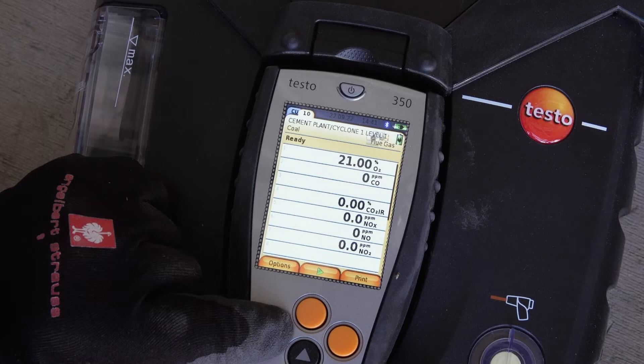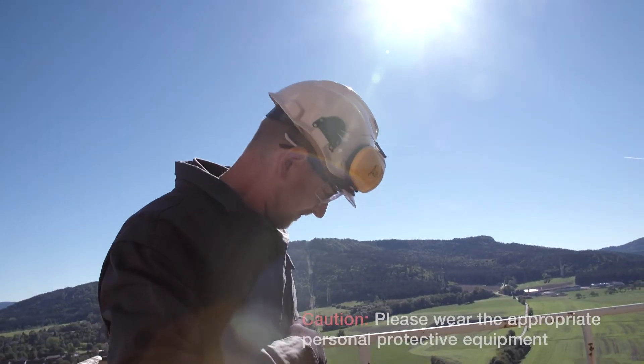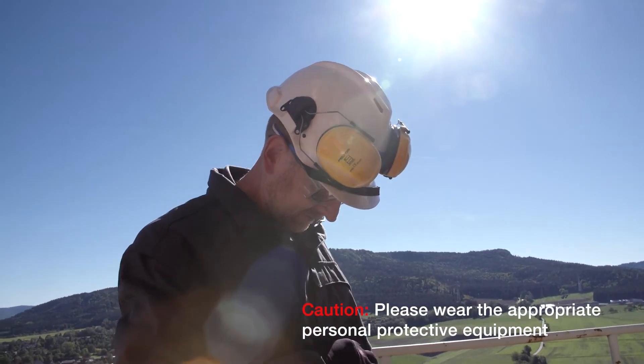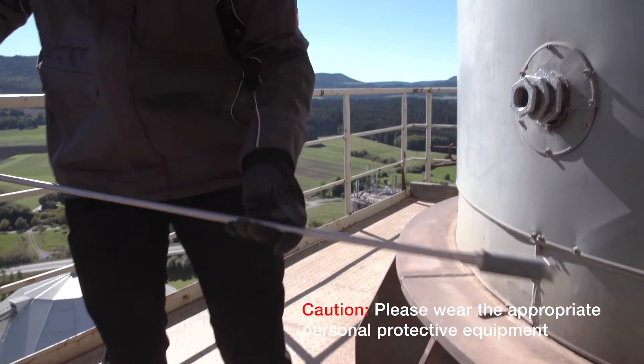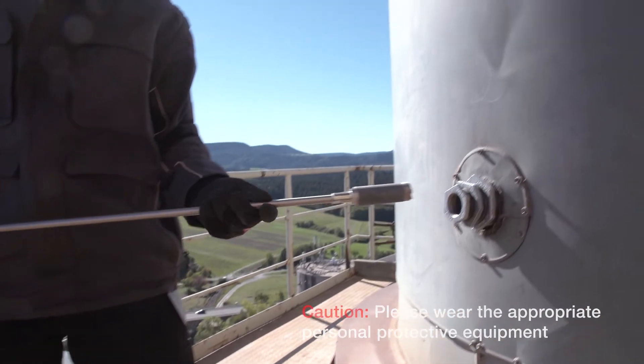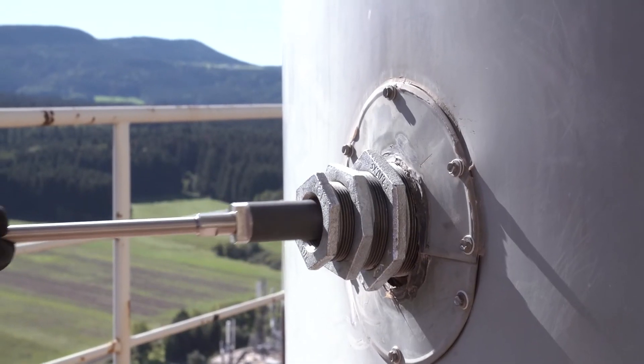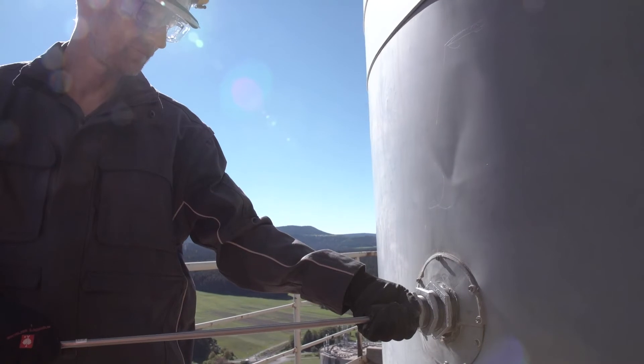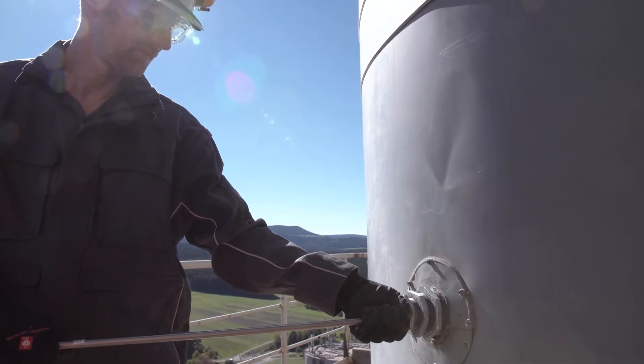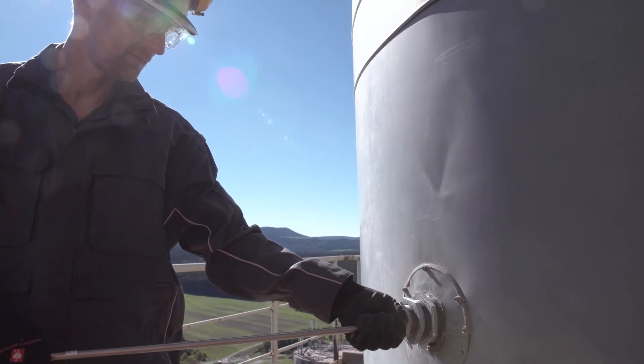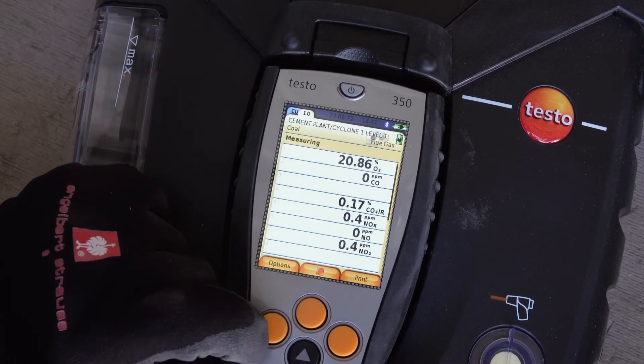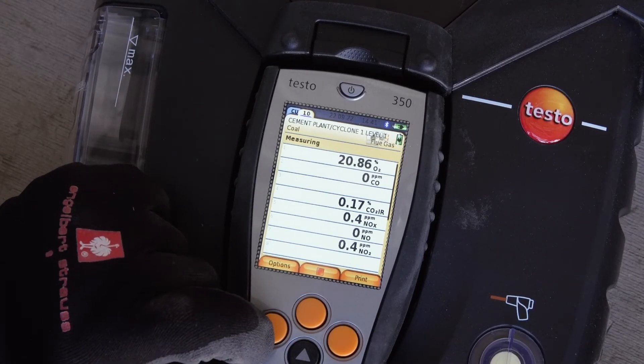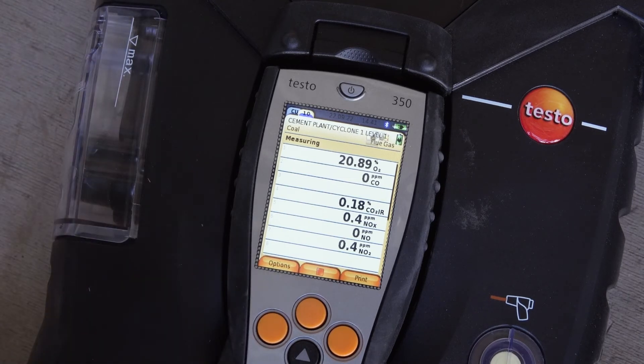The industrial probe with pre-filter is used for this measurement. It is connected directly to the exhaust duct of the plant, and the probe tip should be positioned in the center of the flue. The exhaust gas measurement can then be started by pressing the middle button (green arrow).